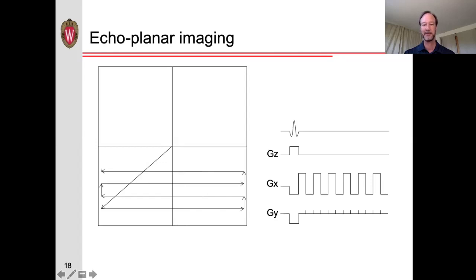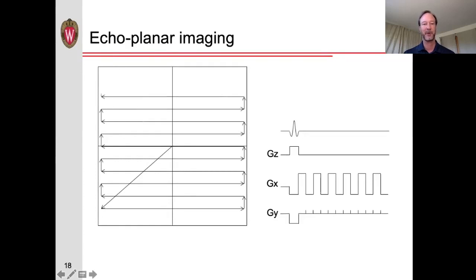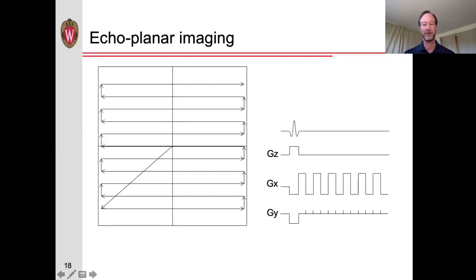The benefit of EPI is that within a single RF excitation we're acquiring the entire image — very efficient. Whereas the gradient echo technique takes several minutes to acquire a whole volume, in EPI we're acquiring the entire slice in about 20 to 40 milliseconds, and the entire volume of the head in approximately one to two seconds, depending on the resolution.